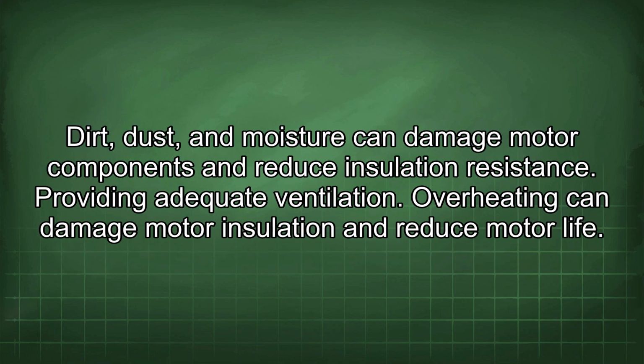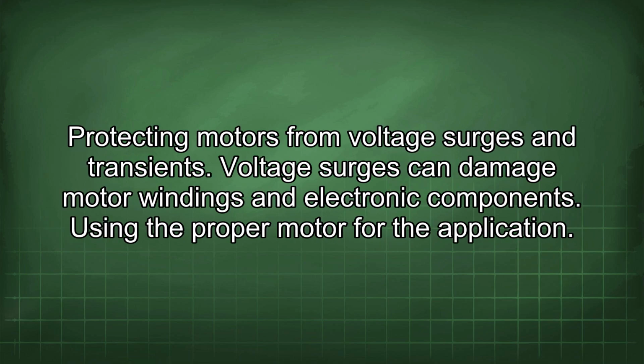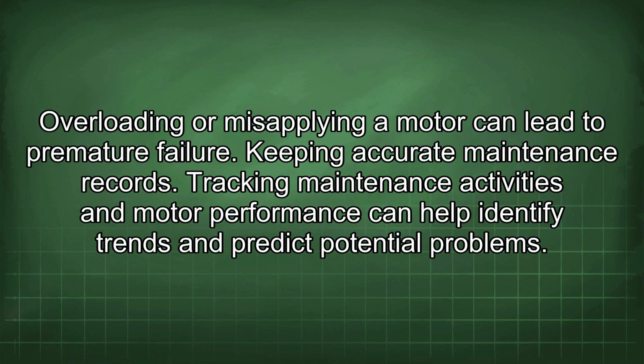Dirt, dust, and moisture can damage motor components and reduce insulation resistance. Providing adequate ventilation: overheating can damage motor insulation and reduce motor life. Protecting motors from voltage surges and transients: voltage surges can damage motor windings and electronic components. Using the proper motor for the application: overloading or misapplying a motor can lead to premature failure.